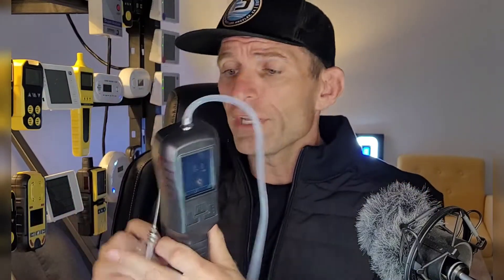All the bells and whistles: large battery, USB recharge, and an easy barb — three-millimeter stainless steel barb. You can pop on the silicone tubing that it comes with, just like that. And it comes with a three-inch stainless steel probe, so you can do very fine helium gas leak measurements at will.